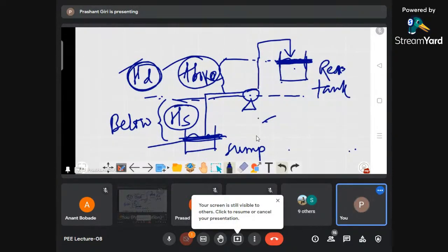डिस्चार्ज हेड इज व्हॉट अगेन, distance from the center of the pump to the level of water in your overhead tank. So discharge head you can manipulate. It is totally based on the horsepower of the pump. किती कॅपॅसिटीचा पंप तुम्ही वापरता त्याच्यावरती डिपेंड आहे, तो तुम्ही मॅनिप्युलेट करू शकता. पण सक्शन हेड जर एकदा तुम्ही इन्क्रीज केला तर पंपची एनर्जी लॉसेस तेवढेच होतात. आता इमॅजिन करा, आपला जो एक पंप आहे, just forget about the other terms mentioned in the slides, focus here.